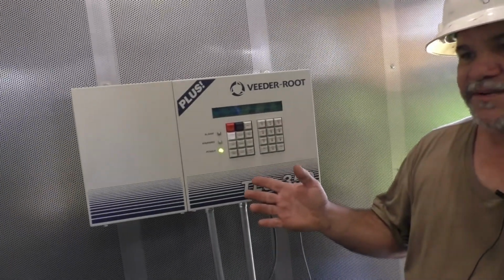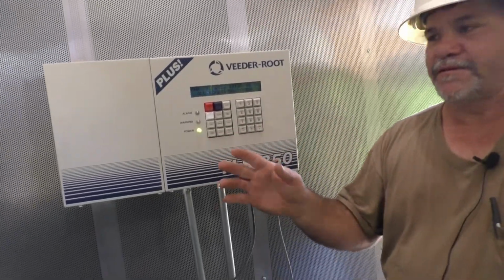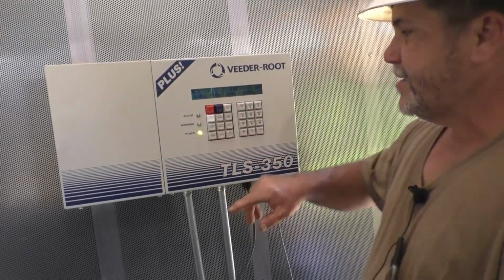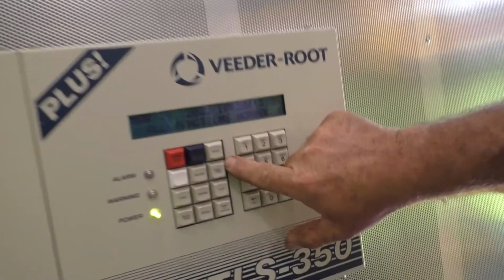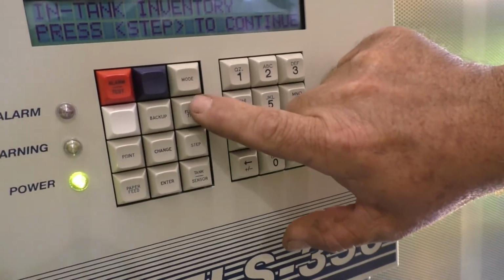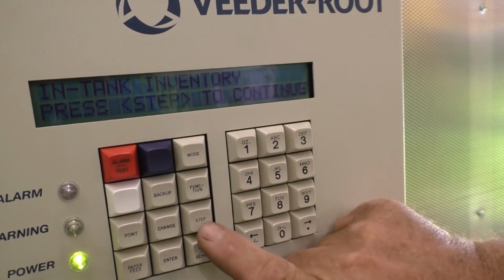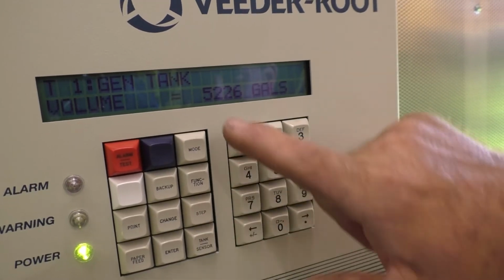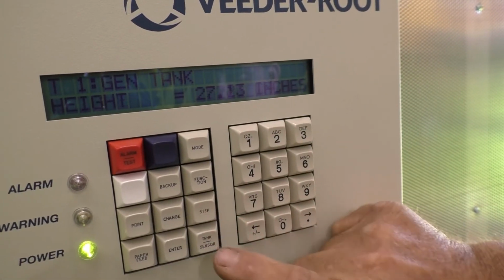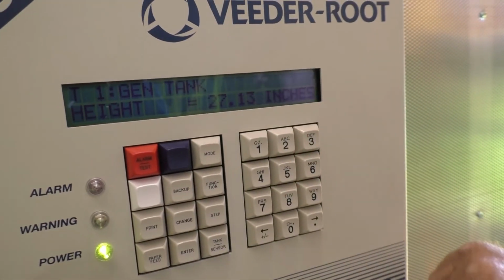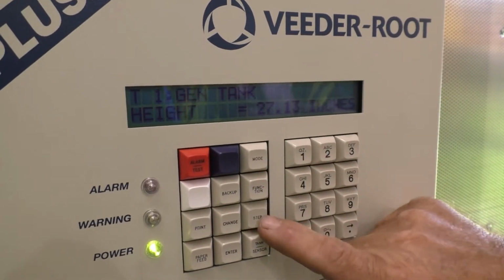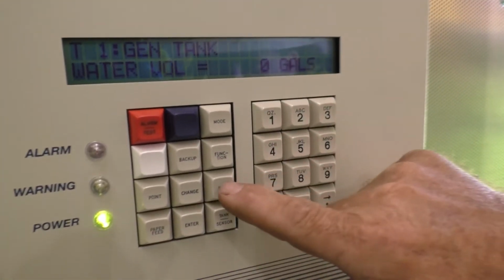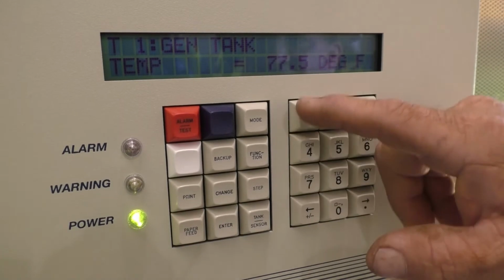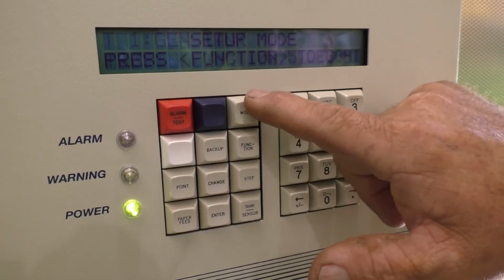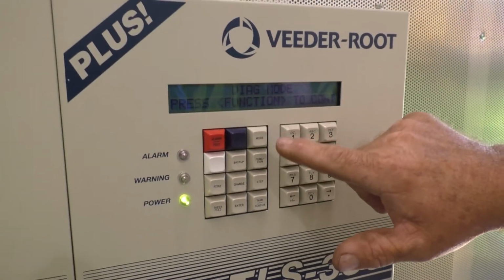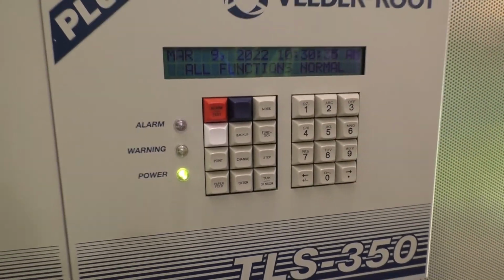And if you want to see the current inventory, you can come up here and hit the function button until it says in-tank inventory. You hit step and it's going to tell you the gallons. If you hit step again, it'll tell you how many inches are in there. And if you keep scrolling through there, it'll tell you how much water's in there, stuff like that. Temperature you really don't care about. Just hit the mode button until it goes back off.